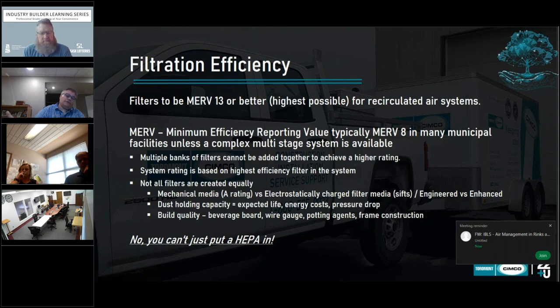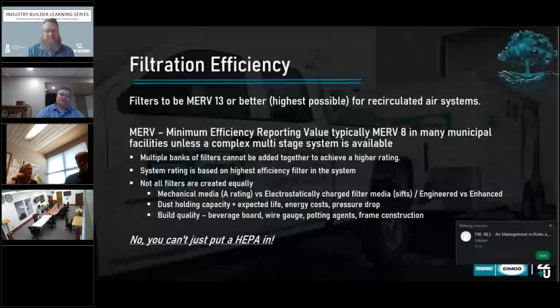You may have four filters that are all MERV 8, but there's a distinct difference from one to the other. One may be a mechanical media engineered to perform at a standard and only get better. Another may be enhanced with a static electricity charge that attracts dust, dirt, and particulate just by an electrical charge. That filter typically may drop from a MERV 8 to a MERV 5 and has to get dirty to perform better.